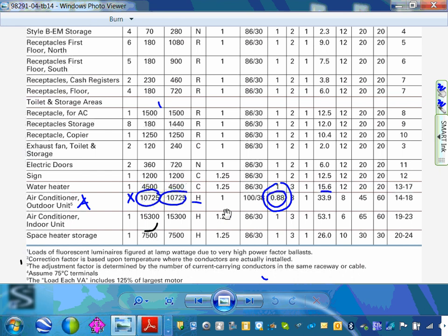Excuse me. This amp, anybody can tell me where this amp came from? Take this number divided by 240. Can you guys verify that this is what you get? Is it? 35.3. Uh-oh. They changed. I know this is from the last. Okay. Well, that's because that first number's different. Oh, yeah. VA load is a little bit higher, so it's calculated. Oh, okay.